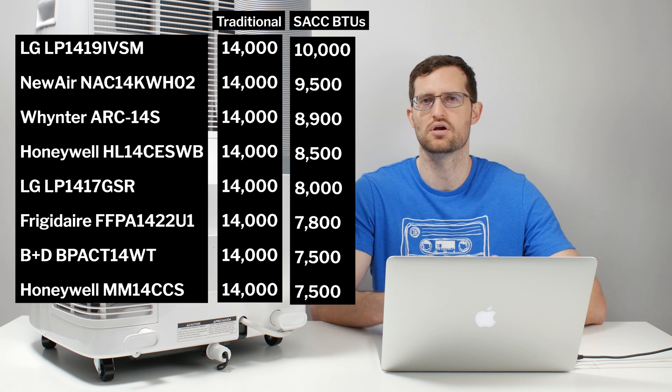Now certain units do still pull in some air from the indoors to cool the condenser even though most of the air that is used to cool the condenser is coming from the outdoors. There's still a little bit of air used from the conditioned room so infiltration air is not completely eliminated but it definitely is less of a problem with dual hose units, at least theoretically it would appear to be so.